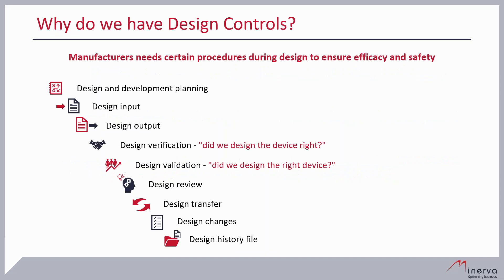All of these procedures have the intention to improve safety and efficiency. For example, the design input includes the intended use of the medical device and the user requirements. Design verification confirms that the design output meets the design input requirements. Design validation ensures that the device conforms to user needs and intended use. We also have the Design History File — the famous DHF — a demonstration that the design was developed according to the approved design plan and FDA requirements. All of these procedures have a relationship to each other.